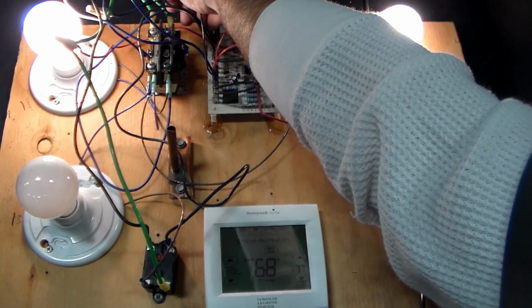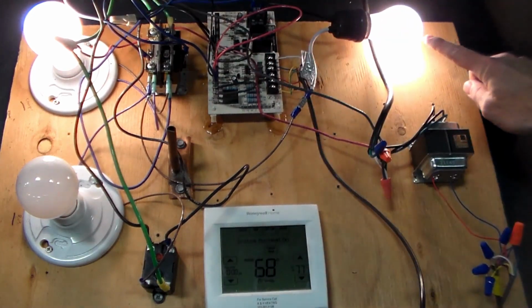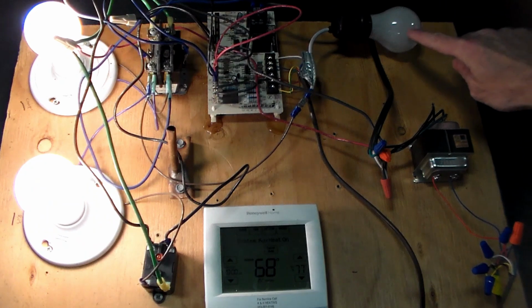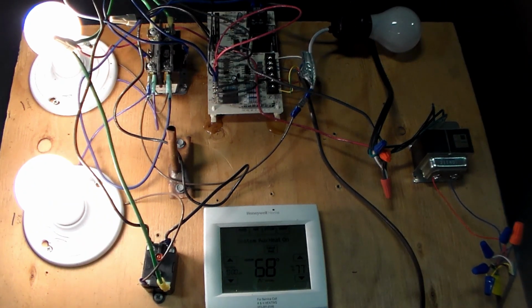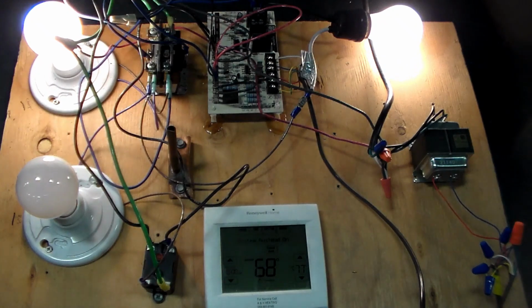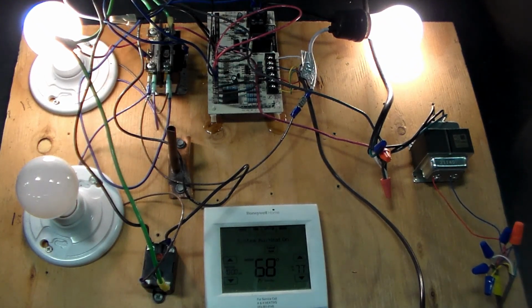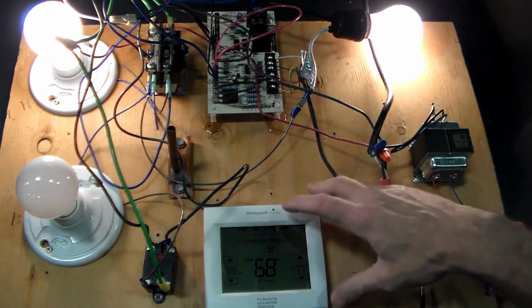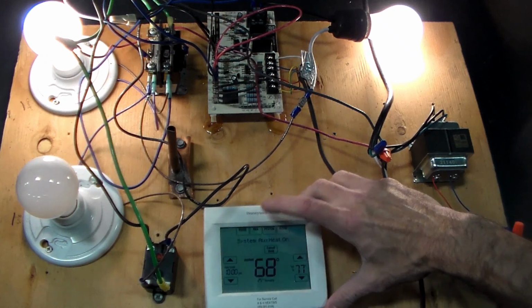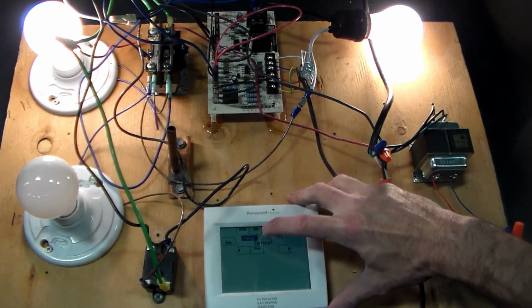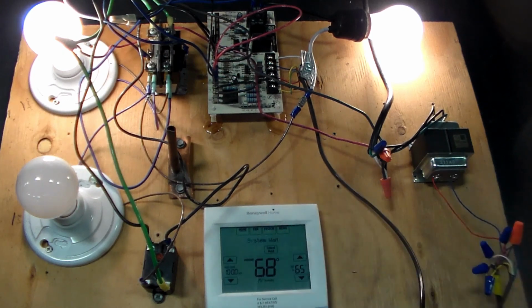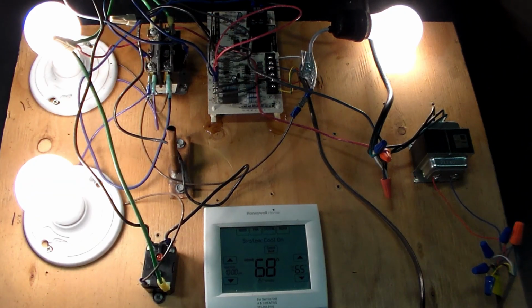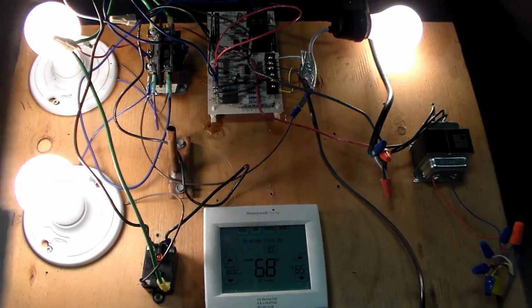When it goes into defrost, as we saw earlier, it's going to kick off the condenser fan. It's going to kick on the reversing valve, switching it to cooling mode until it's defrosted, or until that timer's up in the board, which is 10 minutes. Then in cooling, we're going to have everything actuated. Compressor will be on, condenser fan will be on, and your reversing valve will be on.